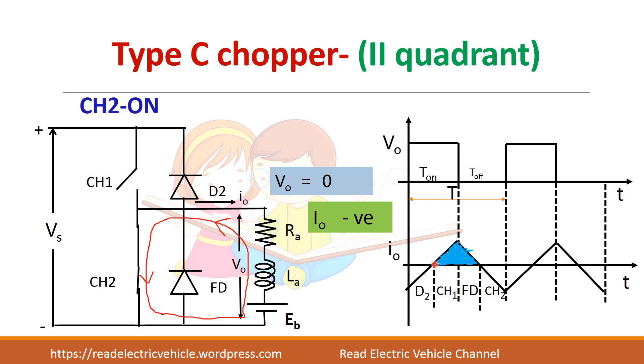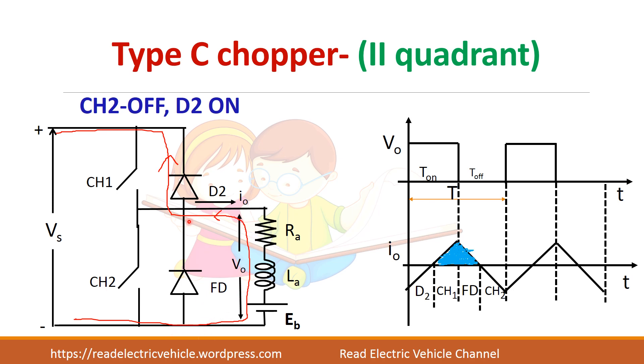In first quadrant operation, when switch one is on, current increases, and when it freewheels, current decreases — but in both cases it remains positive. When CH2 is on, the current flows in the reverse direction and output voltage is zero. When CH2 is switched off, the current then flows through diode D2 back to the supply, and the energy stored in the DC motor is fed back to the supply.